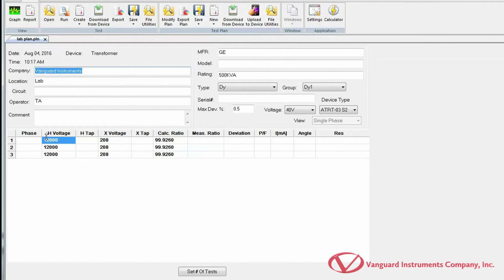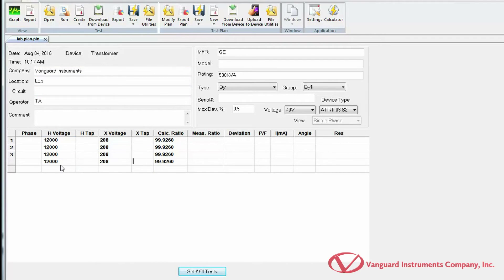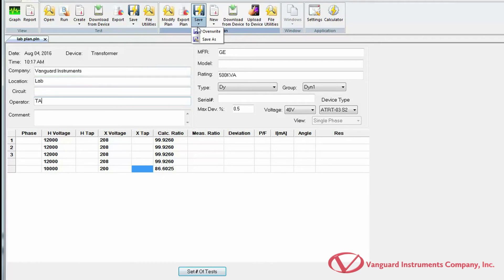Now that the test plan is loaded, you can modify any test parameters as necessary — including header information, transformer type, maximum deviation percentage, test voltage, and the Vanguard turns ratio tester model. This sample test plan is configured to perform three tests. You can change the number of tests by clicking Set Number of Tests, then change H and X voltage values as needed. Once you've made changes, save your test plan by clicking the arrow below the Save icon. Select Save As to save as a new test plan, or Overwrite to overwrite the existing one with your changes.